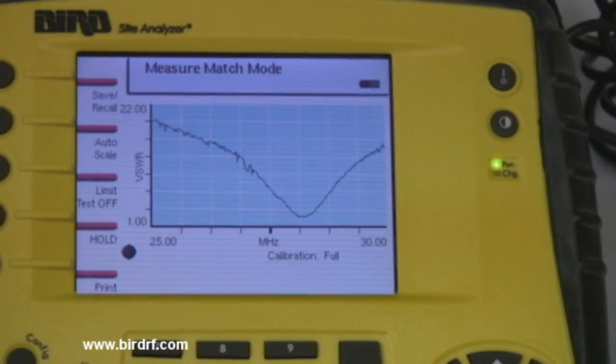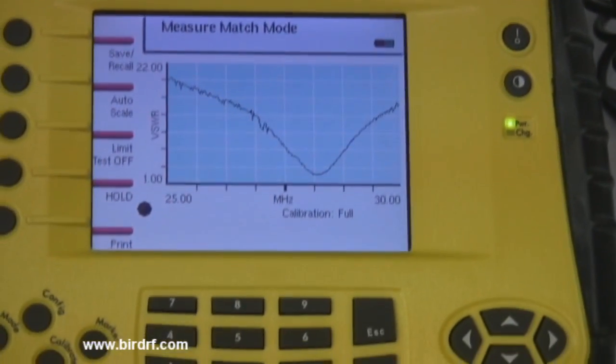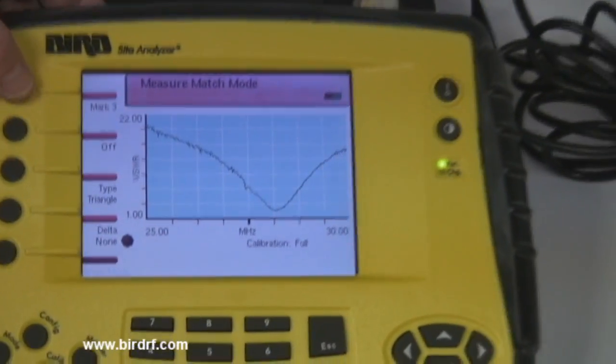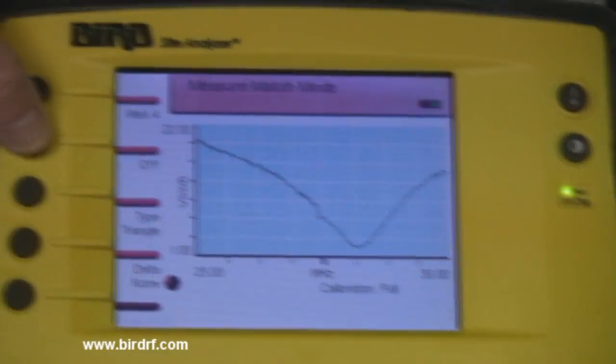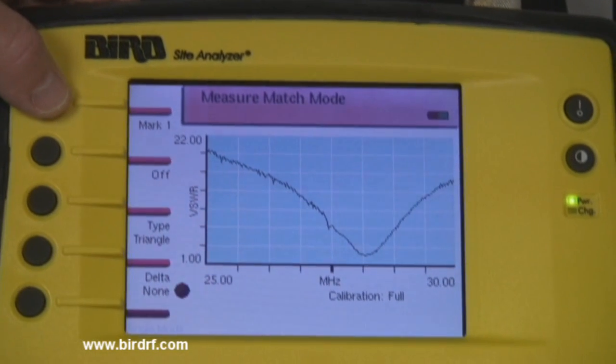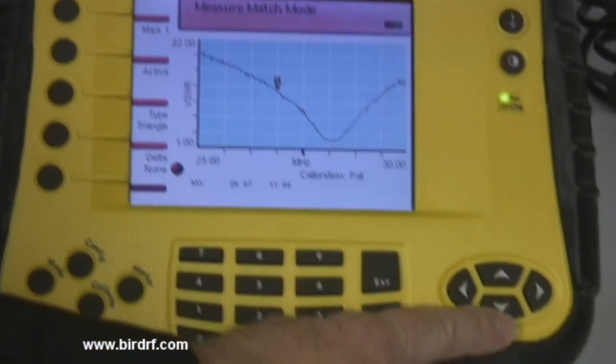To mark the minimum, press the markers mode located in the bottom left corner of the Site Analyzer. Press the marker button located on the left hand side of the Site Analyzer screen until marker 1 appears on the top button. Then select the active button, the second button down to activate marker 1.